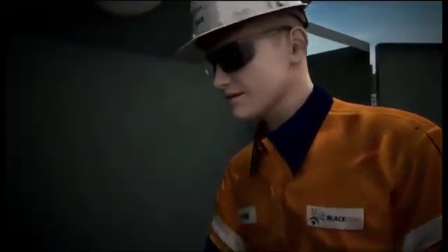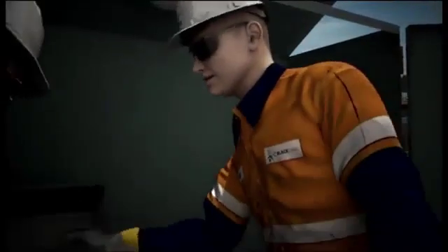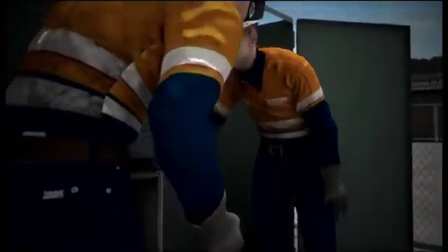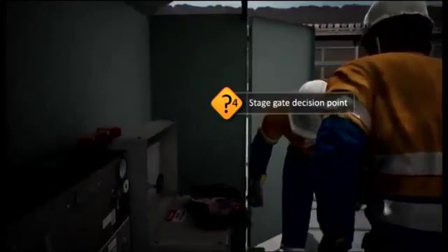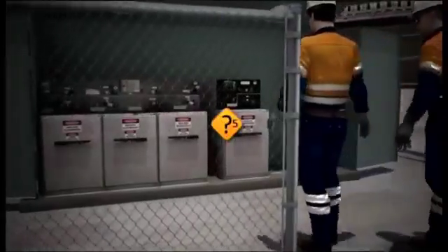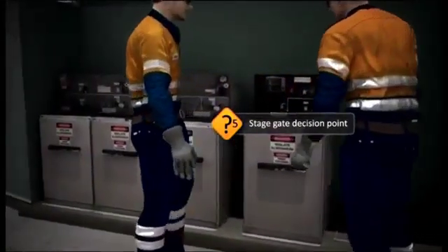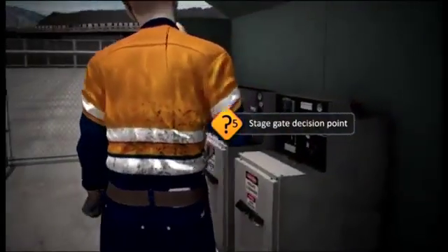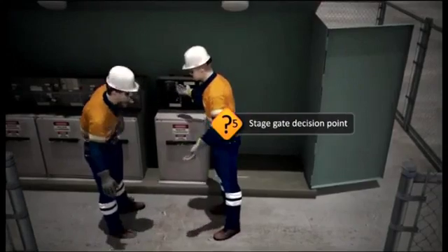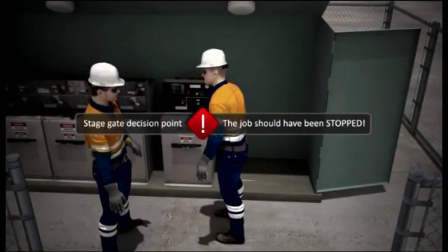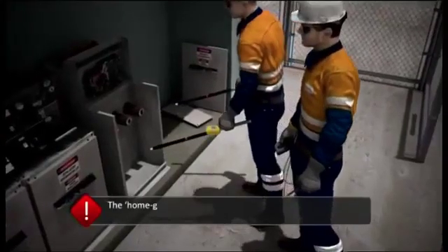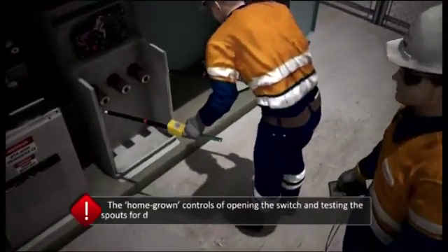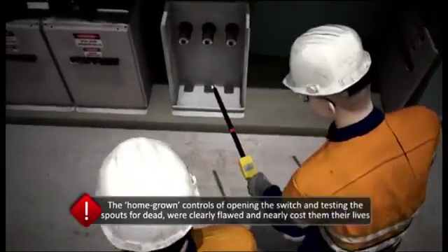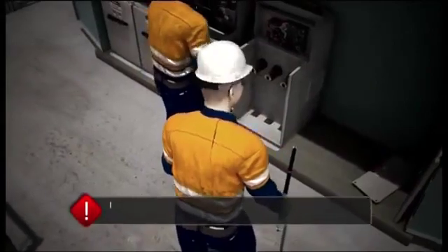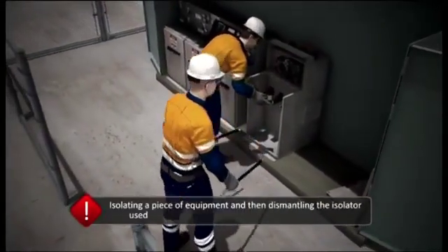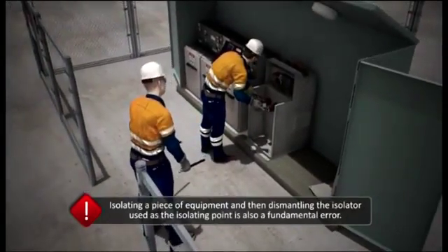To attempt to pry the mechanism over a mechanical interlock that was designed specifically to prevent its removal is the worst type of poor practice. This should never have been attempted, and again, the decision should have been to stop the job. Finally, the decision to open the high voltage cabinet without following the correct isolation procedures and obtaining the proper permits is a clear breach of practice and can never be tolerated. The job should have been stopped until the necessary authorizations were obtained. The homegrown controls of opening the switch and testing the spouts for dead was clearly flawed and very nearly cost them their lives. It should also be noted that isolating a piece of equipment and then dismantling the isolator used as the isolating point is also a fundamental error in isolation practices.